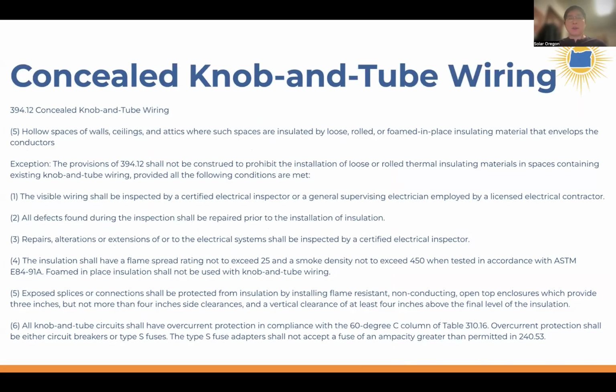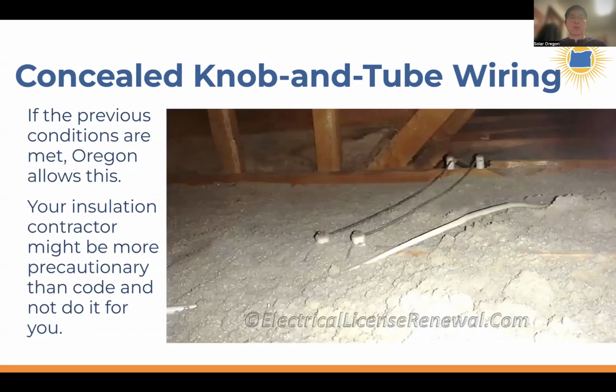Oregon is also unique in having a special provision for knob and tube wiring. Commonly you hear that knob and tube wiring must be replaced, but Oregon says if an electrician looks at the wiring to confirm it's safe, and you follow six provisions, then technically the knob and tube wiring isn't dangerous. So you can drill and fill a wall with insulation even with knob and tube wiring inside the stud cavity, and insulate an attic with knob and tube wiring present, provided an electrician has verified these conditions are met. So you can do this in Oregon; in many other states, you cannot.